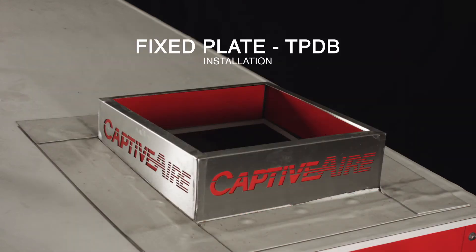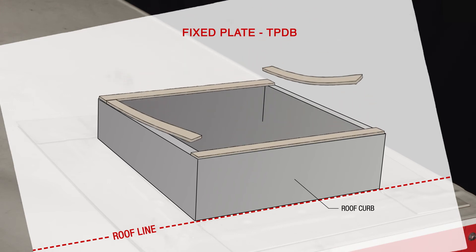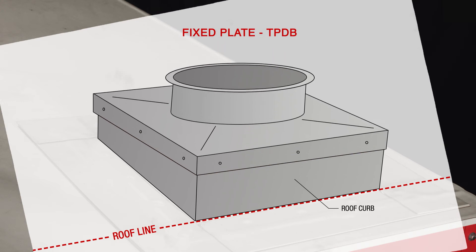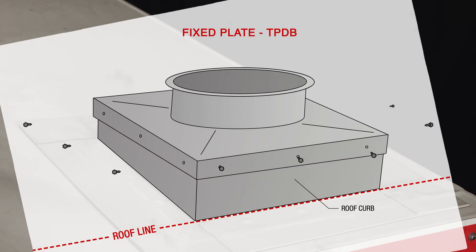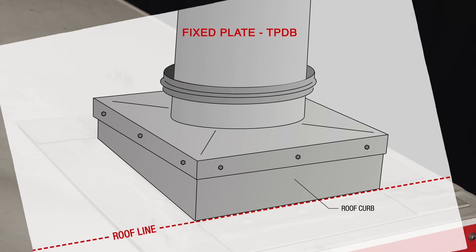To install a fixed TP DB plate, you must first add gasket material to the edges of the top of the curb as shown. Then set the transition plate on the curb. Lastly, secure the plate to the sides of the curb using three self-drilling fasteners per side. Do not attempt to mount a fan to this transition plate, as it is designed for continuing duct runs.